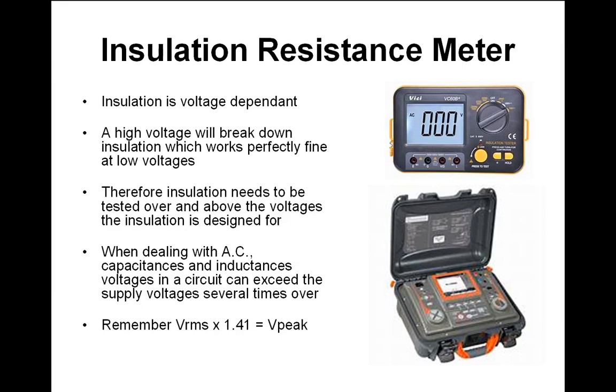And again, when you turn it off and the magnetic field around the coil breaks down and it's got nowhere to go, or there's a big resistance somewhere across the switch where you've turned it off, you can get voltages which are 5, 6, 7 times higher than the operating voltage. So if your motor runs on 240 volts and you just switch it off and it hits a peak on the waveform, you could be looking at about 3, 4, 5,000 volts for a very short moment in time. It's not even milliseconds, possibly nanoseconds or microseconds, around about there. But for a very short period of time, it could cause a lot of problems. And that's something to bear in mind. Again, when you've got an insulator, you have to make sure that, ideally, whatever potential voltage you're likely to come across is dealt with.